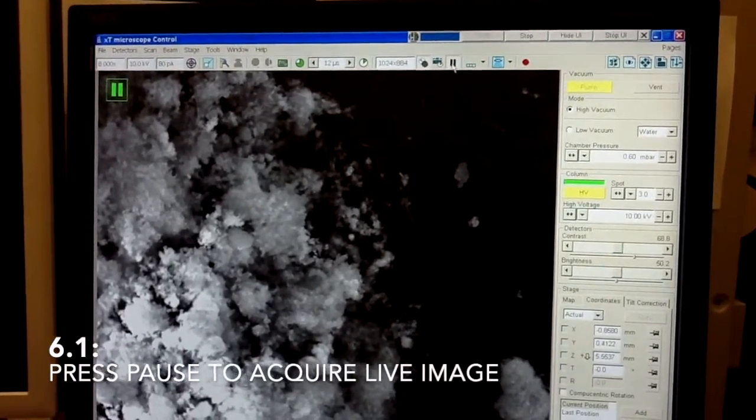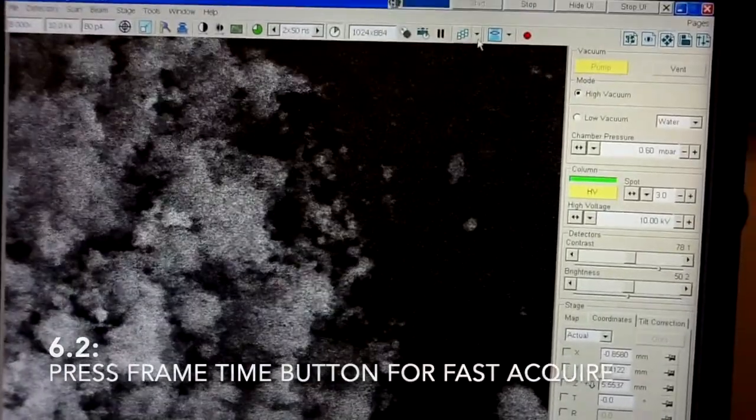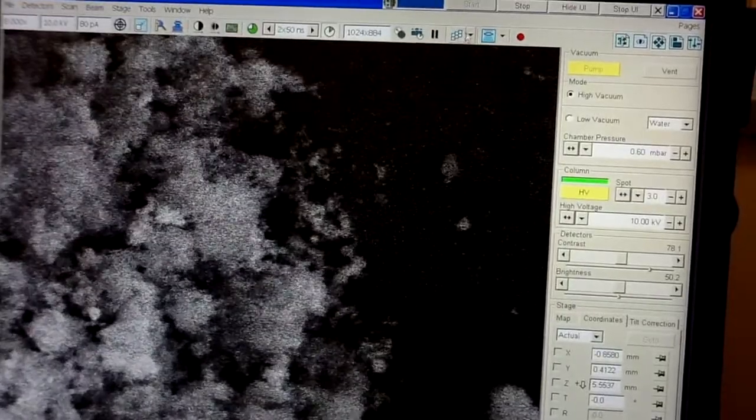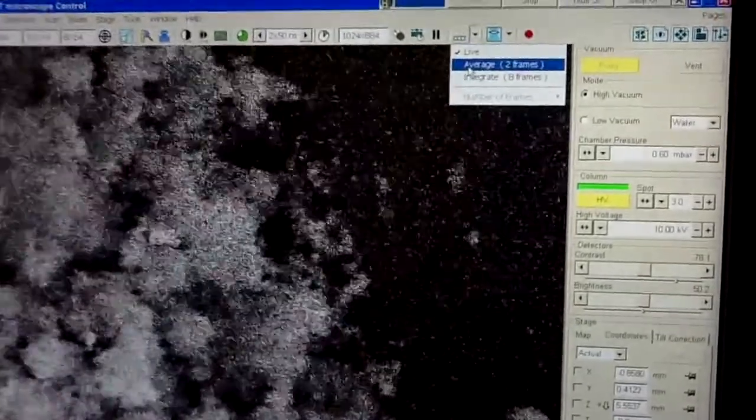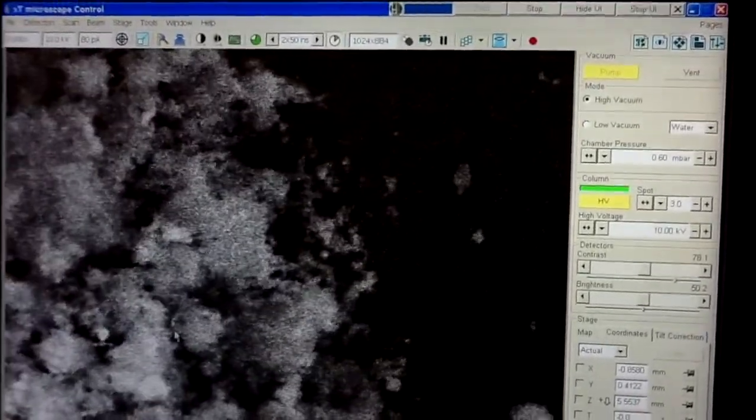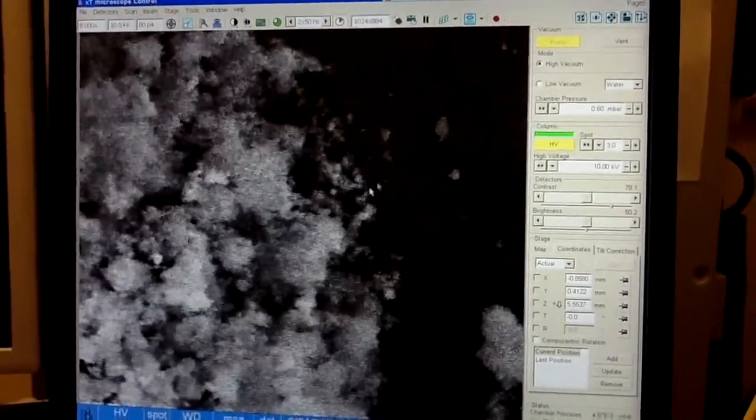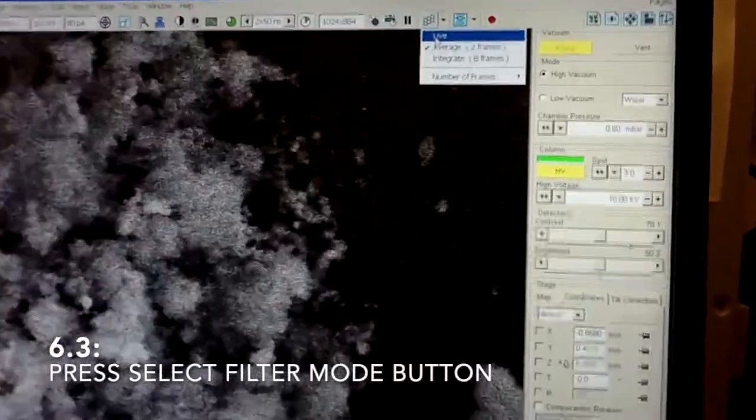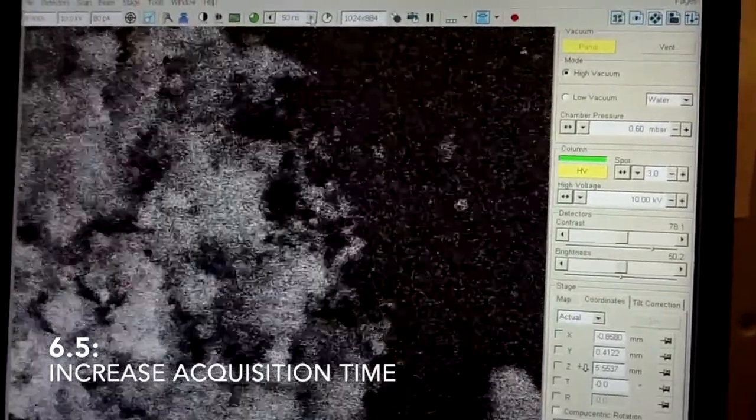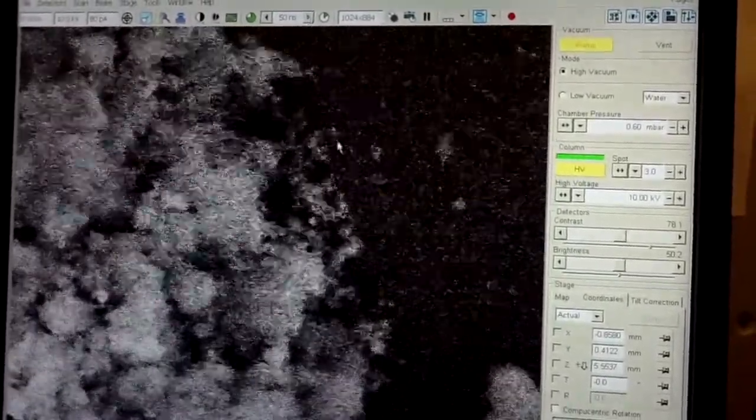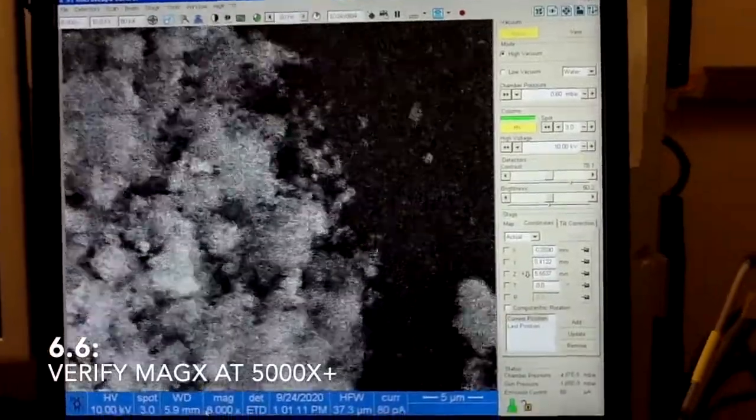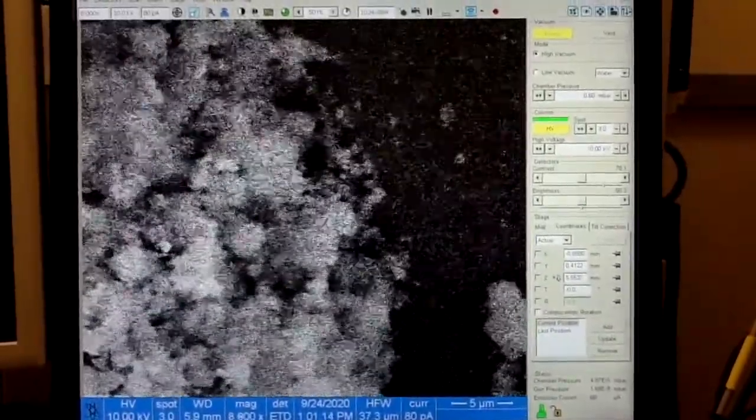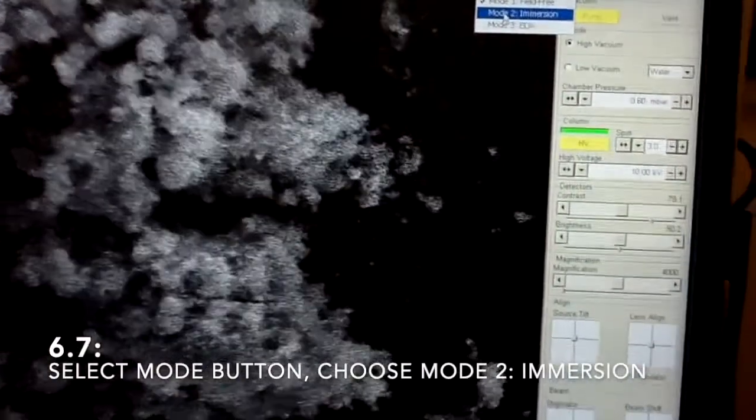First thing, start to acquire live image again. If you press this one, it will be a fast acquisition. Whenever you press this one, you will see that this icon changes from live, which is this, to average, which is this. This will give you a better quality. However, if your sample drifts or moves, you will have some problems with getting sharp image. So you can use live image and maybe increase the acquisition time. So now to switch to the immersion mode. First of all, you need to be in magnifications at least 5,000 or higher. So we are at 8,000 right now. It should be okay. Go to the immersion mode.